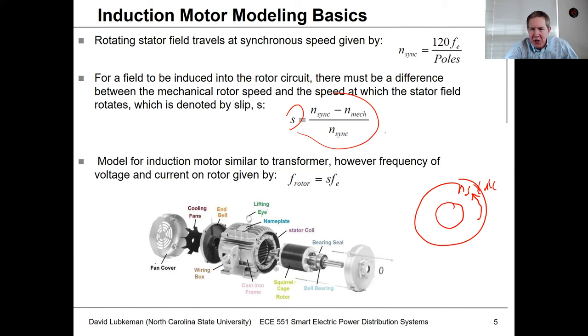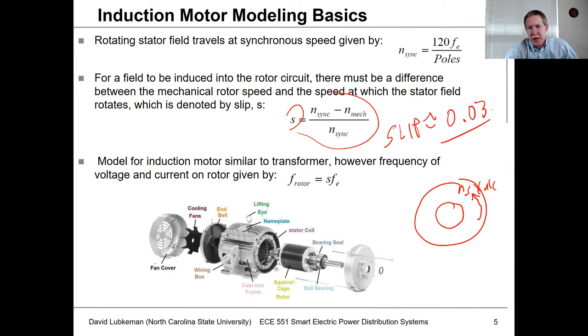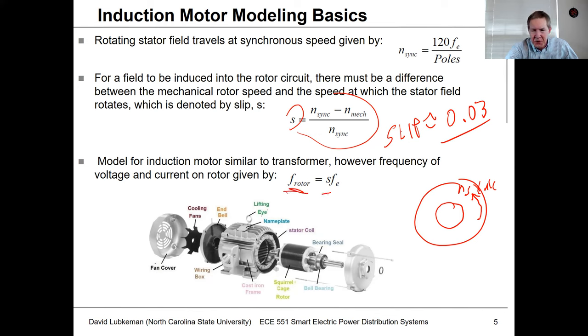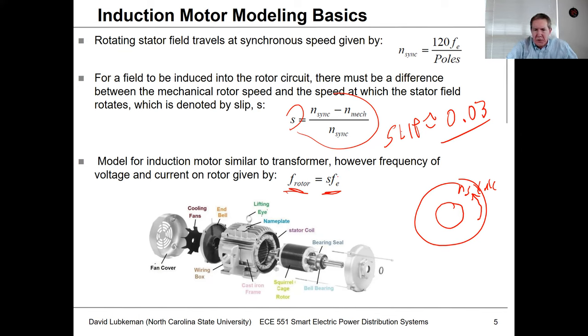It's not possible to have useful induction motor operation in steady state with the rotor traveling at the same speed as the synchronous speed — there has to be some speed differential. Normally, when machines are operating in steady state, the slip is going to be about 0.03. Once you have the slip term, you can get the frequencies on the rotor circuit as the slip multiplied by the electrical frequency associated with the stator.